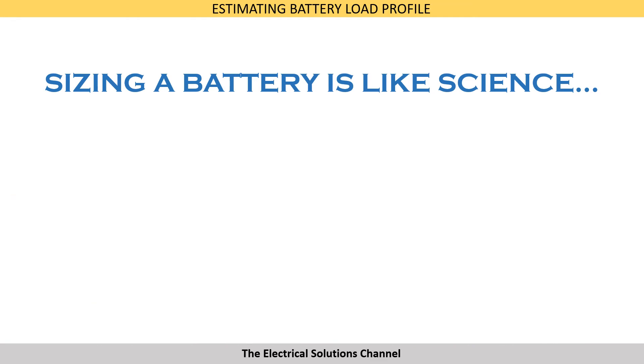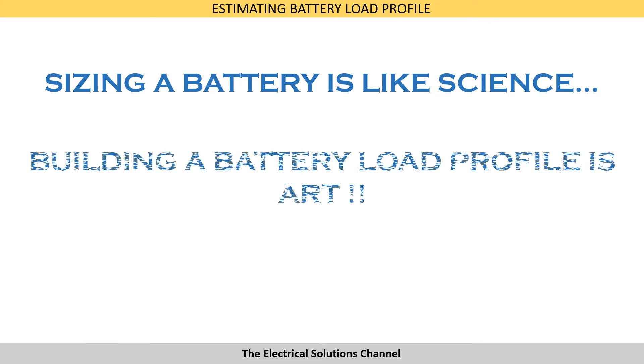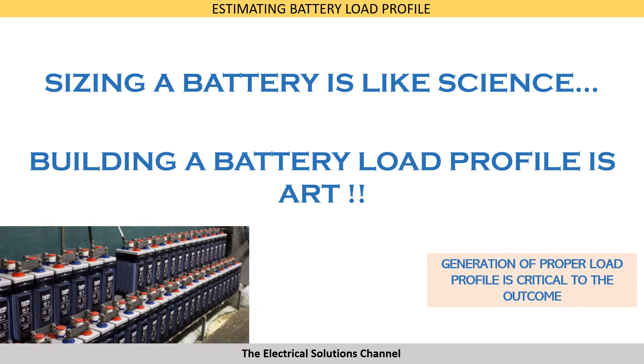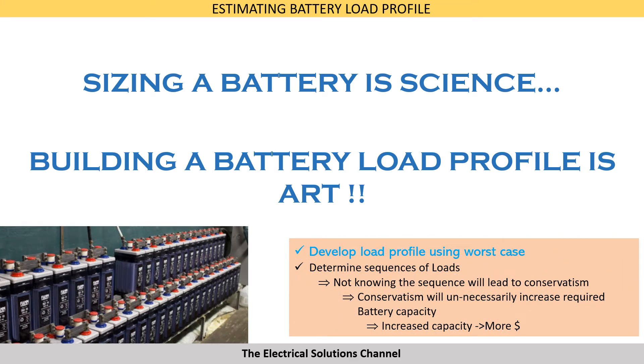However, building a battery load profile is like art. Generation of a proper load profile is critical to the outcome. We should develop the load profile using the worst case and determine the sequence of the loads. Not knowing the sequence of the loads will lead to conservatism, which will unnecessarily increase the required battery capacity and result in a costly battery.